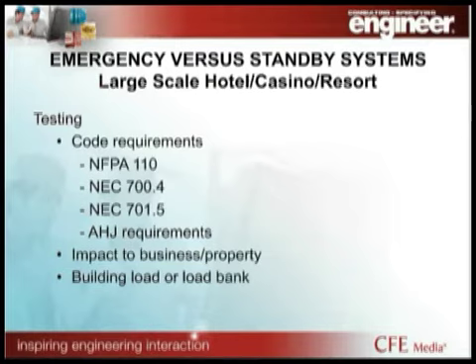And then, building load as a load bank, it really offsets cost. Having the capability of hooking in an additional load is a big benefit. Being able to leverage the optional standby loads for a facility to make sure that you can really drive the generators up to 80% if you want to do that on an annual basis, just to really clear them out.